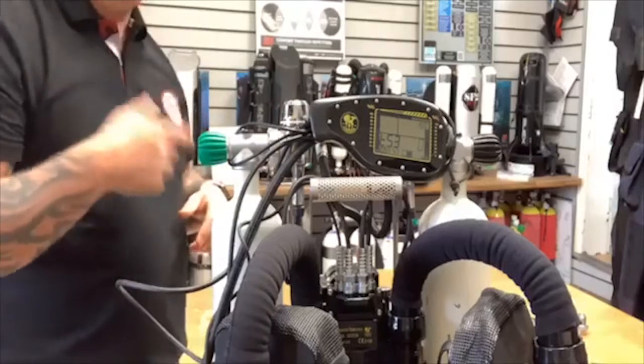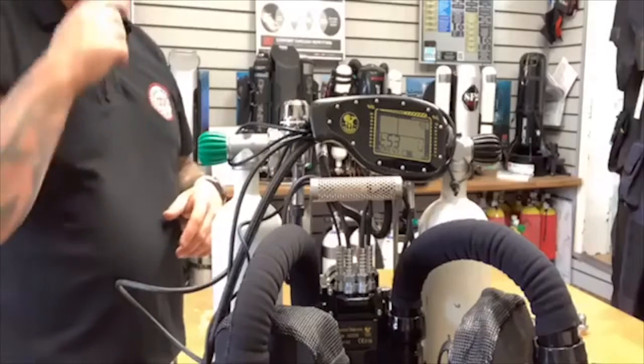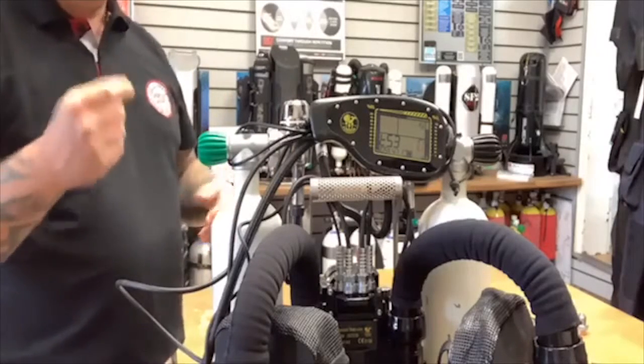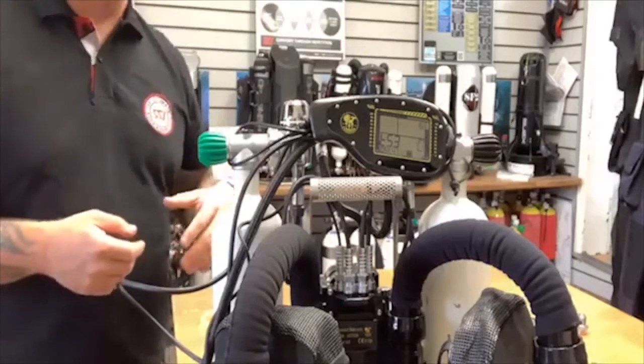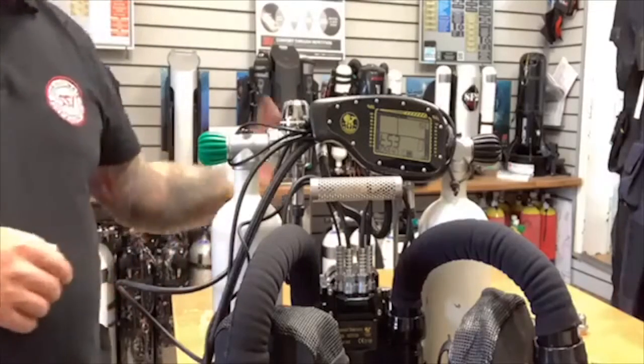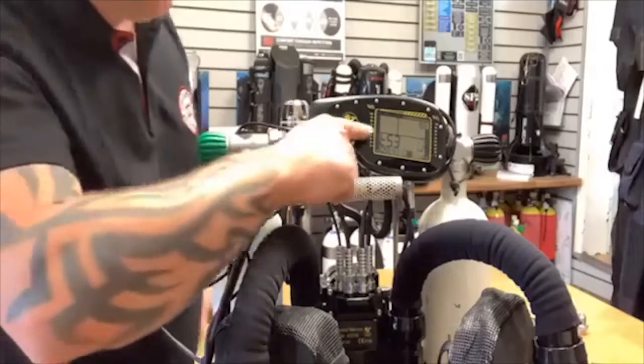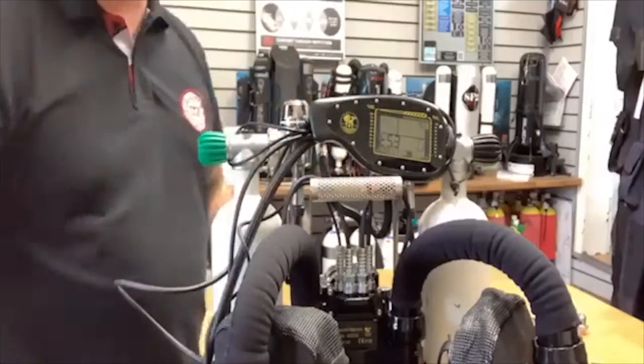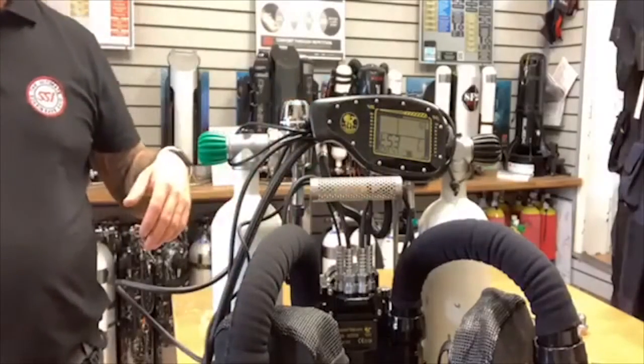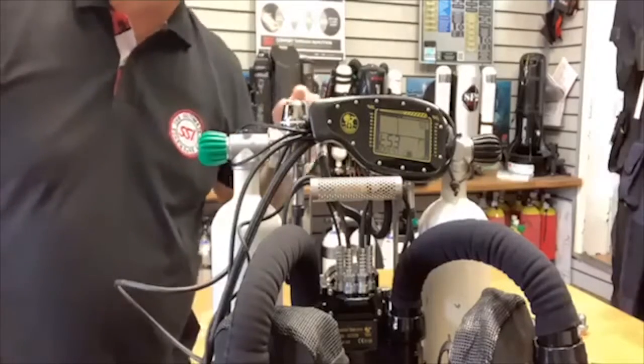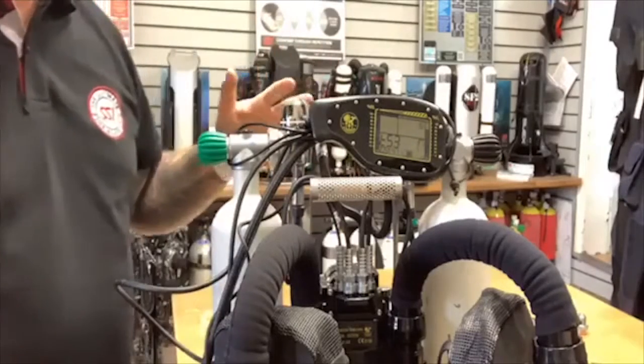So you can hear it now injecting plenty of gas to do the high calibration. You'll hear a stop, then you hear another type of noise, and that is the diluent going in. So oxygen was first, now it's adding diluent. And you can see our little progress indicator on the top, just letting us know where it is in its tests. So it's injecting gas, and then I just heard psh, which is one of the oxygen solenoids firing, and that means that this test was passed successfully.